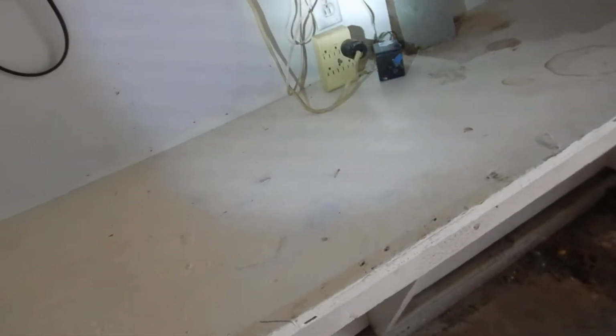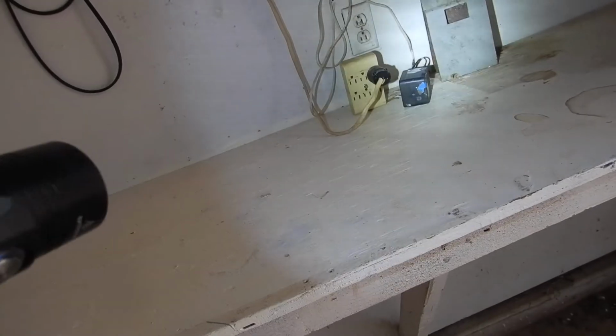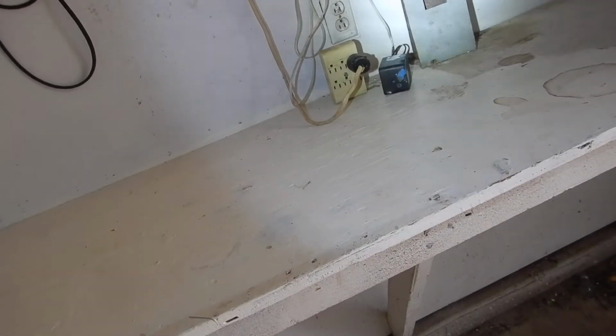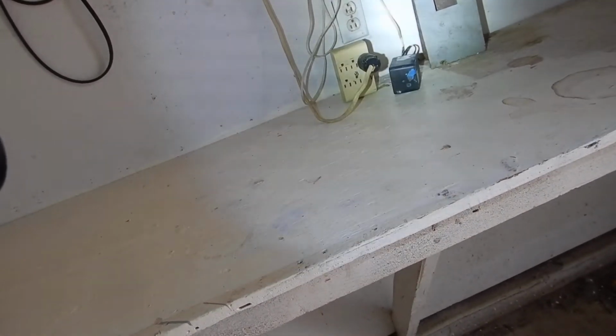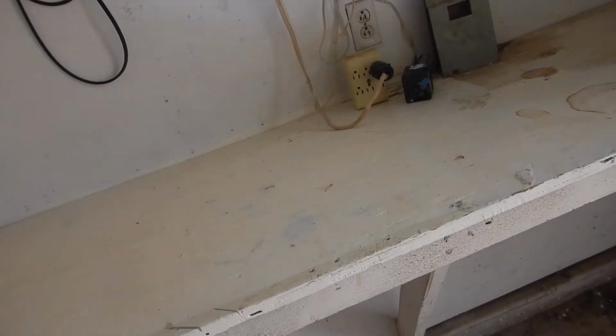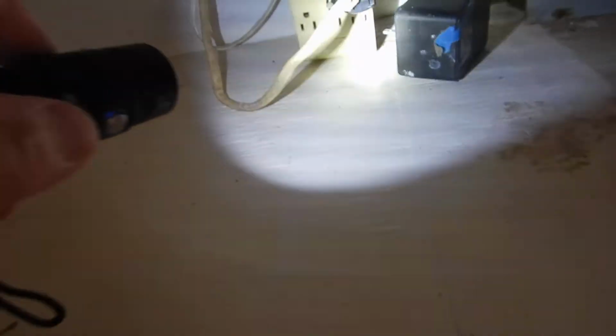So it's got an open knockout. Okay, in fact both of them do. It's not energized. In fact, to energize this would be to bootleg it. You're going to put a breaker box into an electric receptacle outlet. That's just wrong. You take an NM cable and convert it into an extension cord that you could put this into. That's wrong. That's not an extension cord.